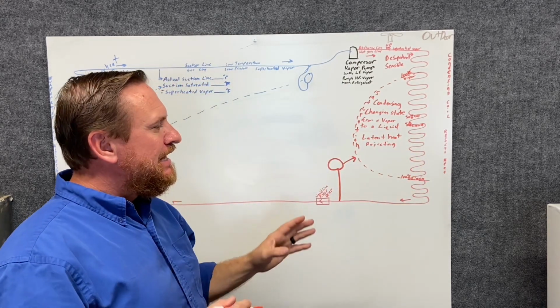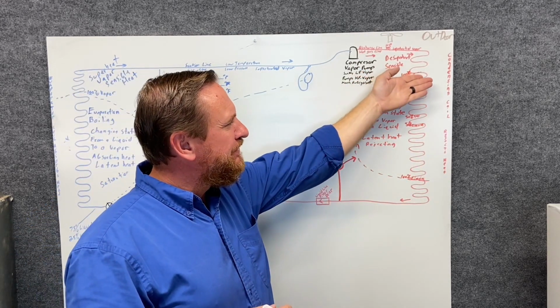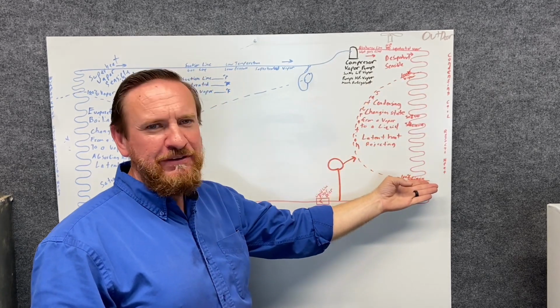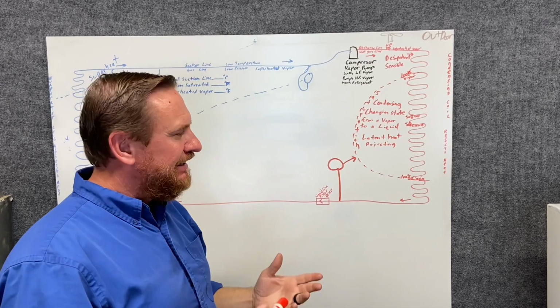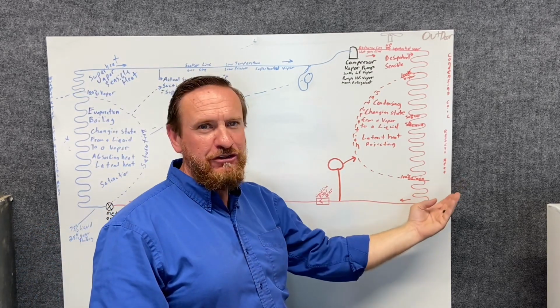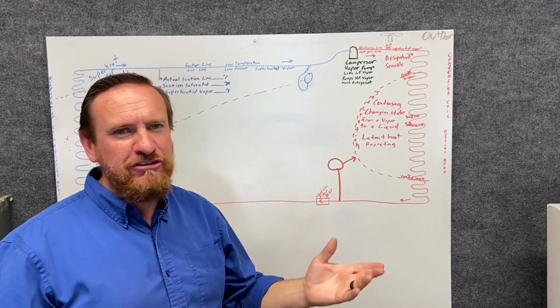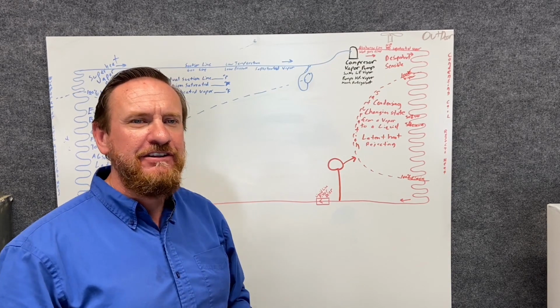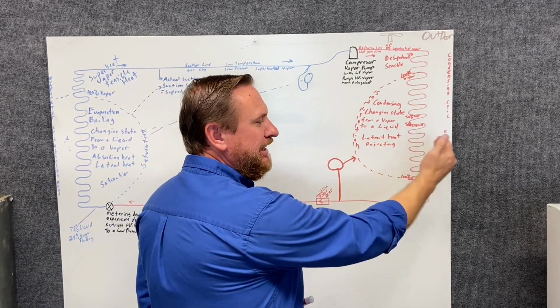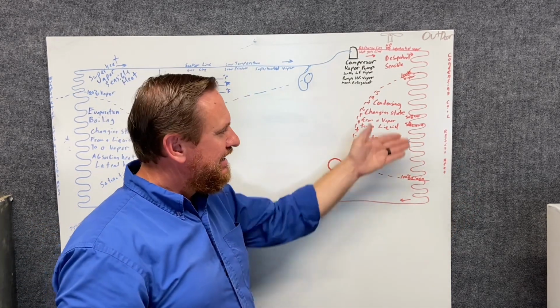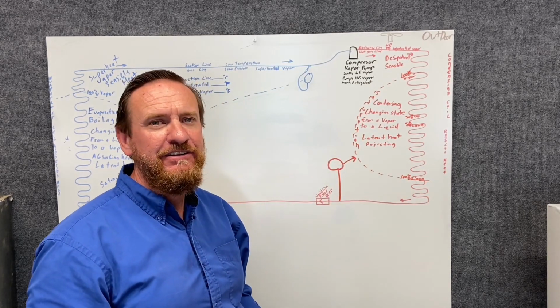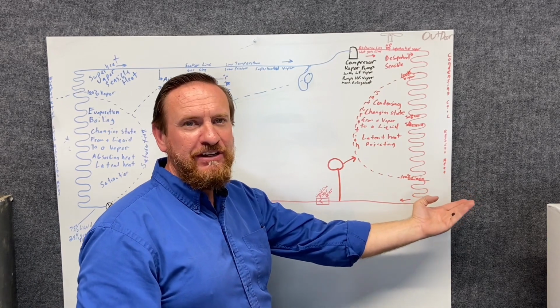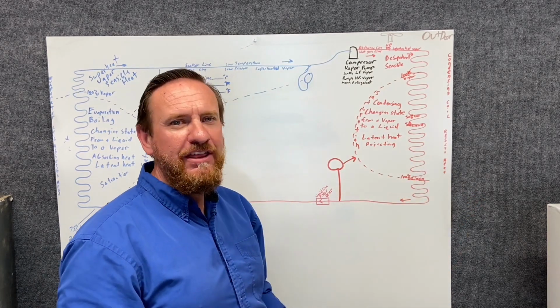Now what's important is after I get it from 100% vapor all the way to 100% liquid, it's still going to be warmer than the air temperature. Let's say the air temperature is 100 degrees. Our refrigerant temperature, just throwing a number out, 115 degrees. So the refrigerant is much warmer than the air. Now that it's completely changed into a liquid, it's still at 115 degrees. The air temperature is 100 degrees. The air is cooler than the refrigerant.